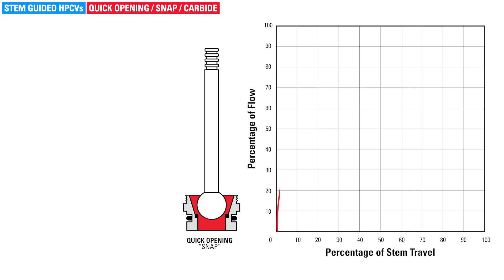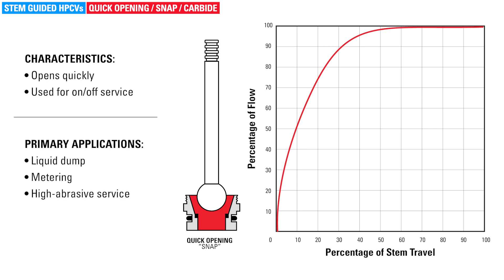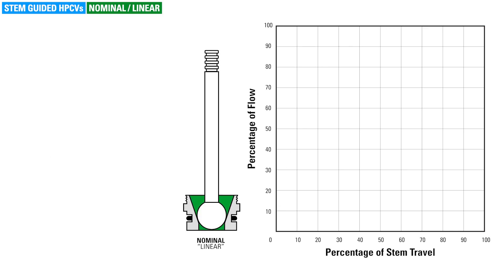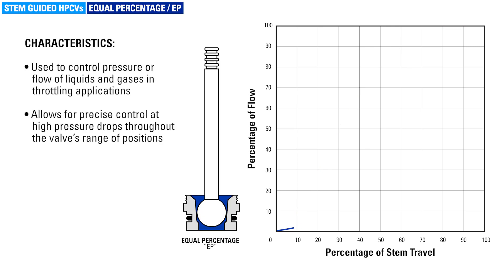Each type of valve trim is characterized by the relationship between the percentage of flow and the percentage of valve stem travel. The differences are not in the size of the ball, but in the design of the seat. Snap, also called quick opening, opens quickly and is used for on-off service — the system goes from open to closed or vice versa instantly. Primary applications include liquid dump, metering, and high abrasive service. Nominal, also called linear, is used for throttling liquids in liquid level control and in applications where water hammering has been an issue and where abrasive material is not present in the stream. Equal percentage is used to control pressure or flow of liquids and gases in throttling applications.